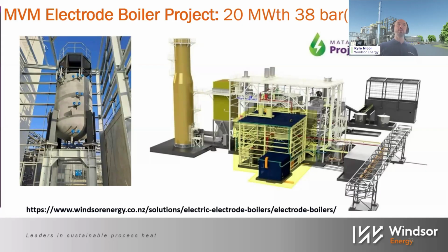Windsor were the EPC contractor for an electrode boiler at Matara Valley Milk, who are a dairy processor in the South Island. This one is a 20 megawatt high pressure electrode boiler that produces 28 tons per hour of steam and was officially opened in 2024. It has a 99.9% thermal efficiency and a 25 to 1 turn down ratio.